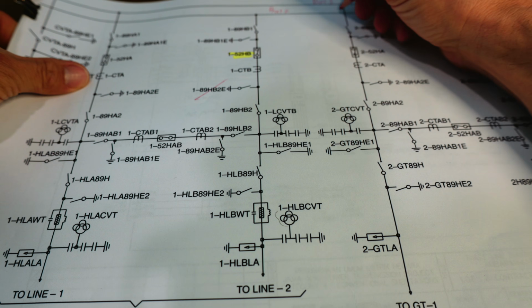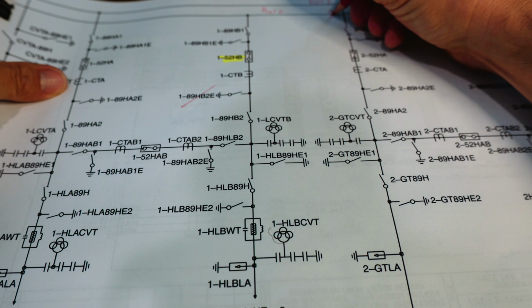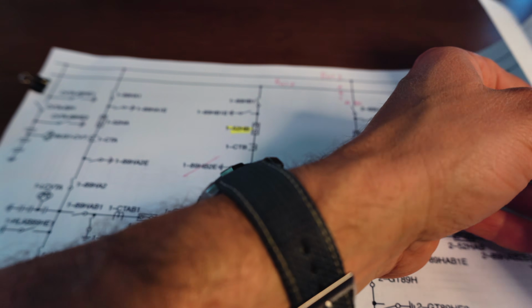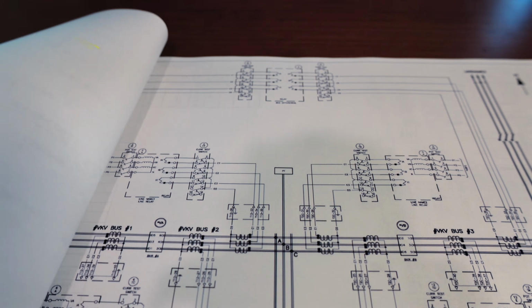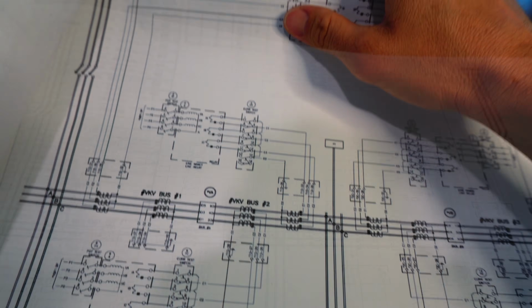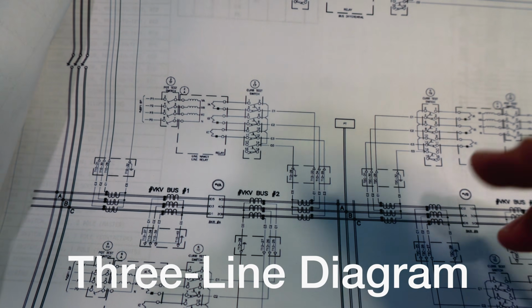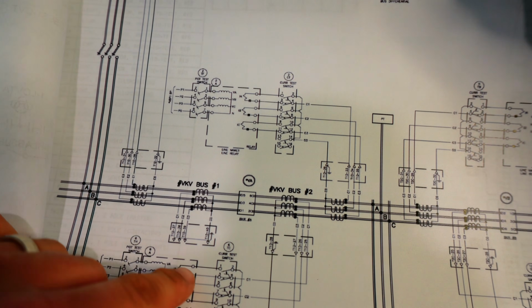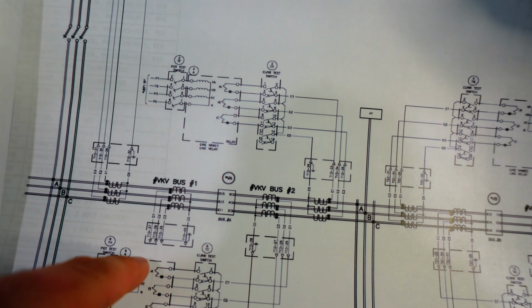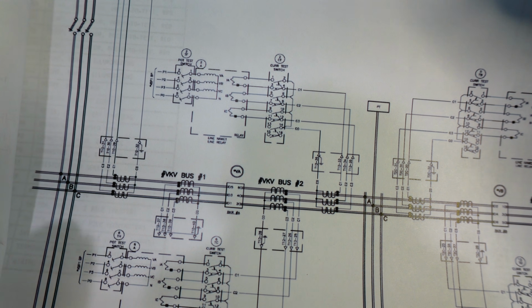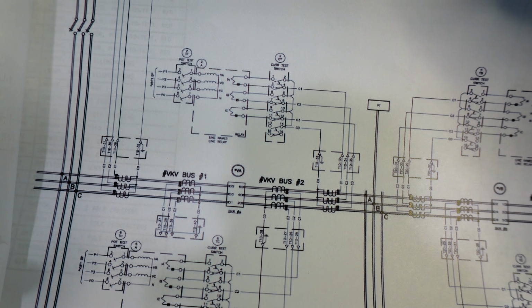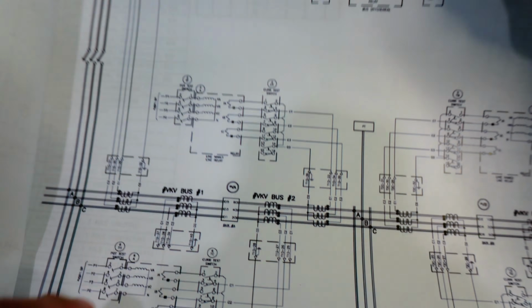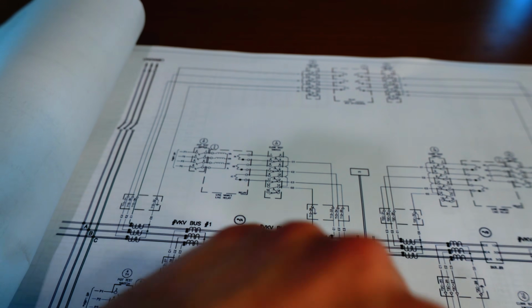So typically this would be, for instance, phase A, B, C. We dive a little deeper in, going from the 30,000 foot view to the 10,000 foot view. We've got 3 lines now, so we're zoomed in a little more. Here we're concerned with the CT connections, because the current transformers reduce the current coming into the relay so we can protect these devices. You can see how that's all connected. So those are 3-line diagrams.